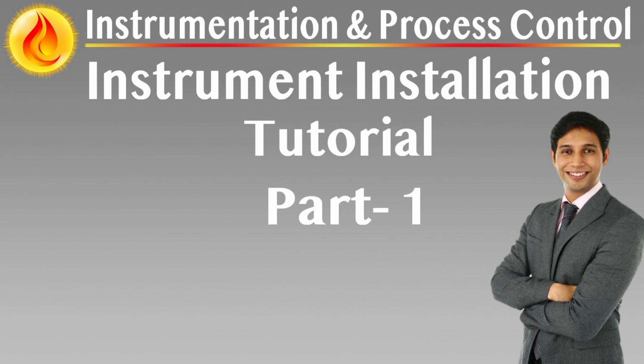Compatibility of heating and insulation with instrument integrity. Heated instrumentation, particularly in low temperature or wax-prone services, requires robust insulation, effective heat tracing, steam or electrical, and removable enclosures for maintenance. Temperature ratings of all tracing elements must be confirmed against process upper design limits. Electrical tracing must comply with hazardous area classification and provide fail-safe operation.